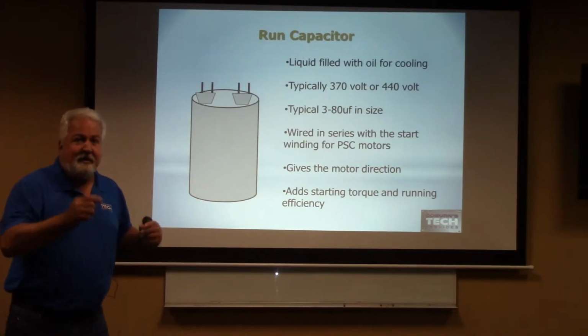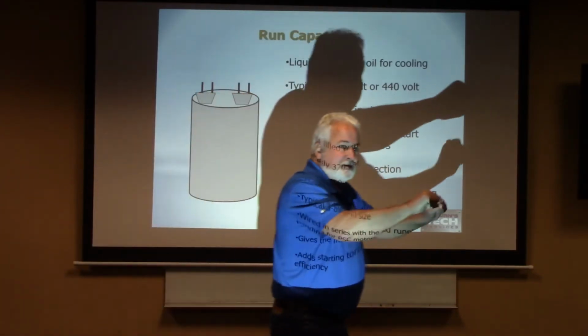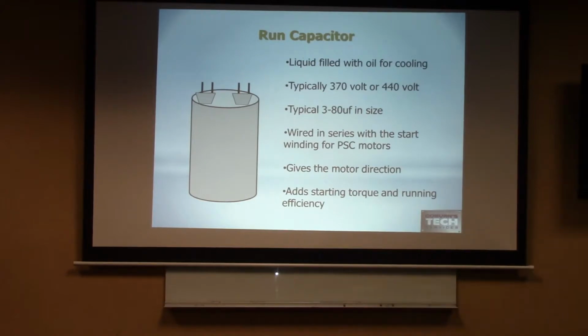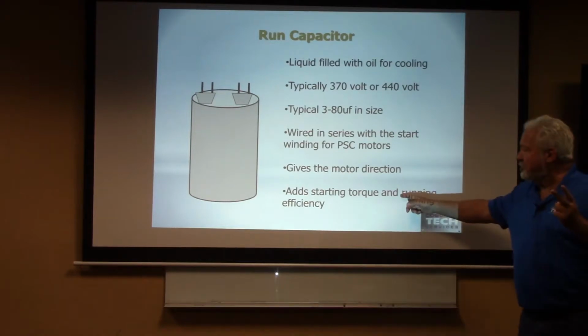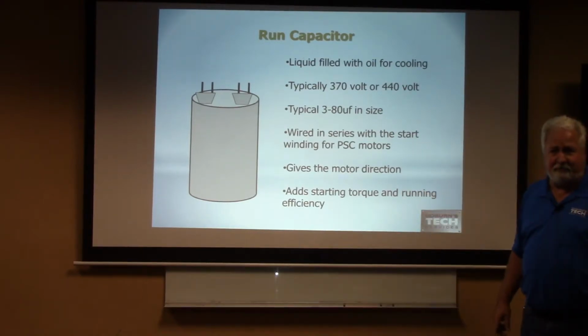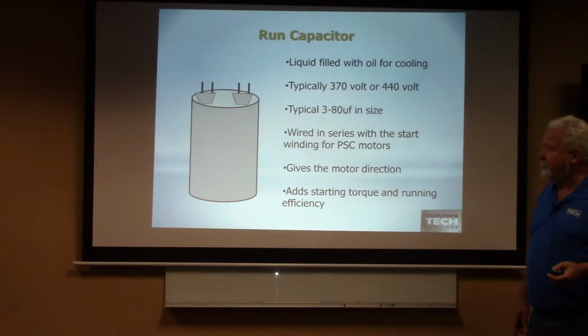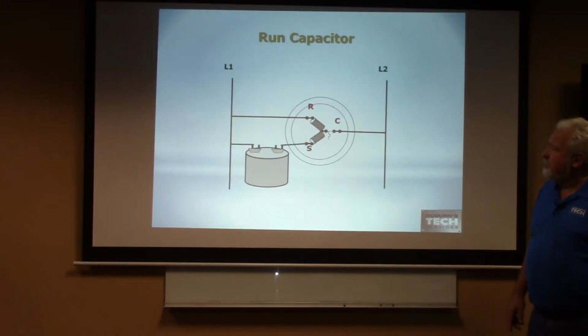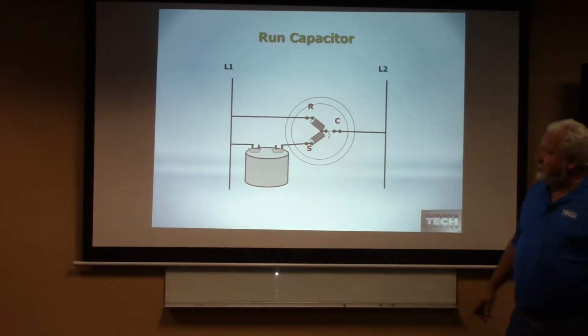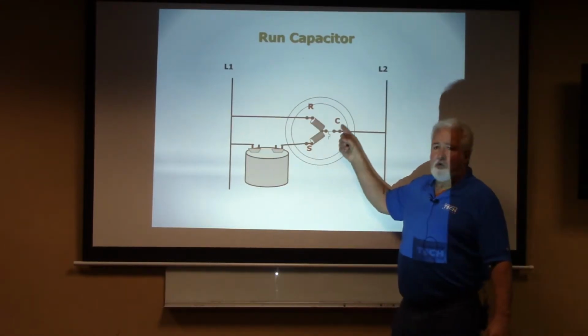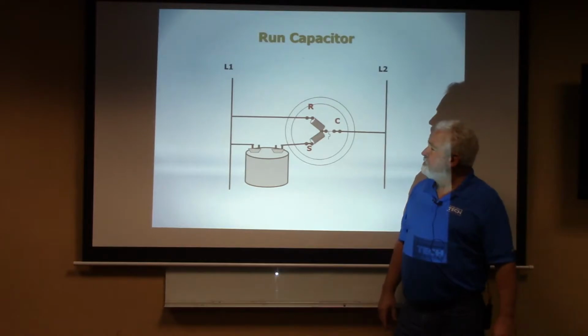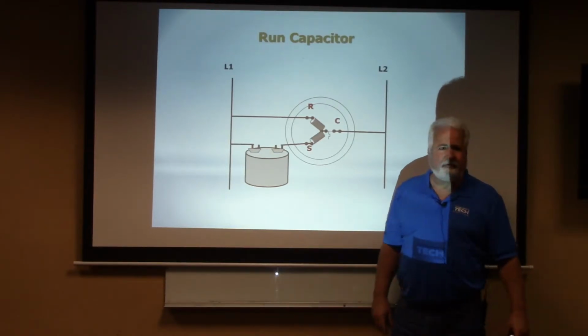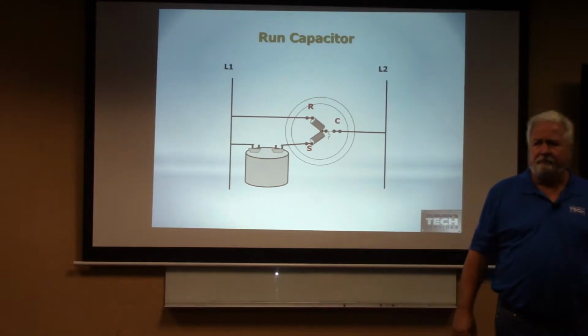He's going to stay in the circuit to help ease that motor and keep it running efficiently. Does that make sense? He's going to stay in that circuit. So he's going to be our run capacitor. He gives it direction, and he helps with that starting torque and running efficiency. Everybody good with that so far? Good. We're going to add something in that mix in a little bit. So there's my run capacitor. It's in series with my start winding. Is that right? Good.